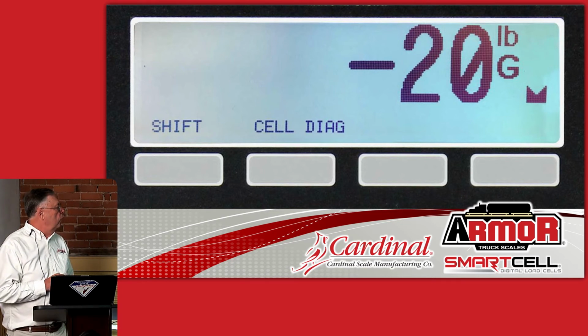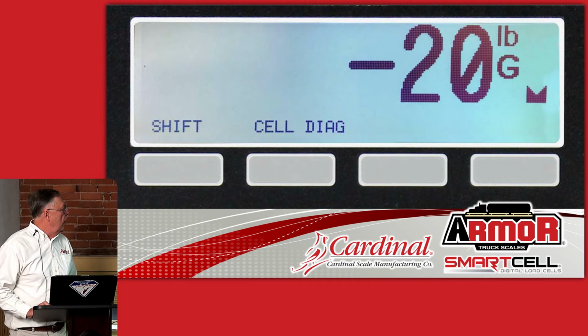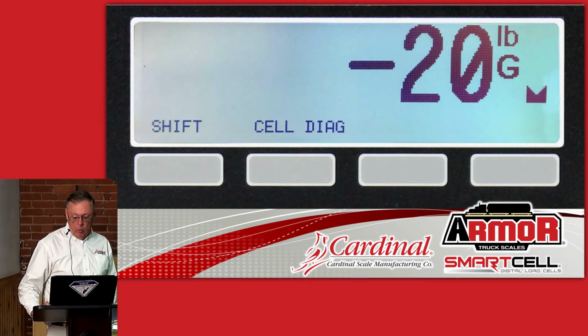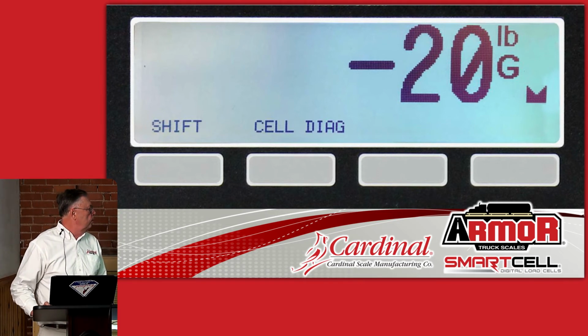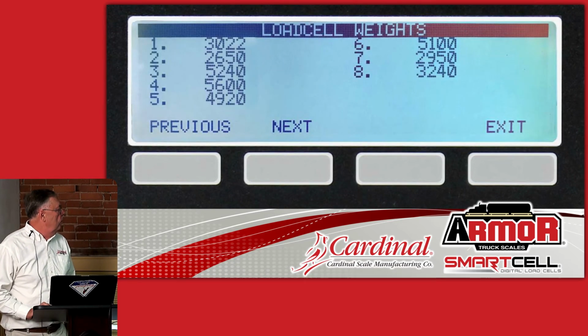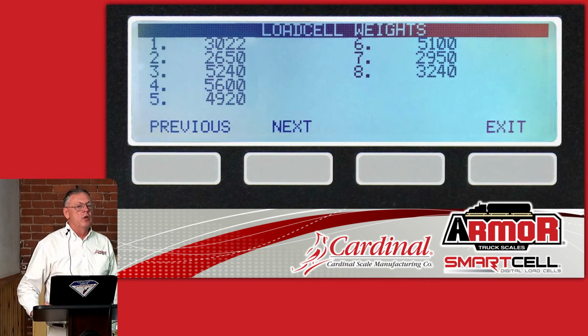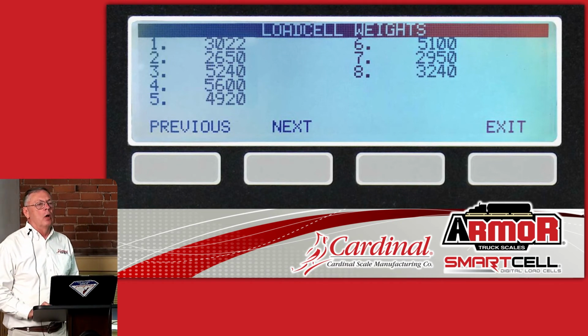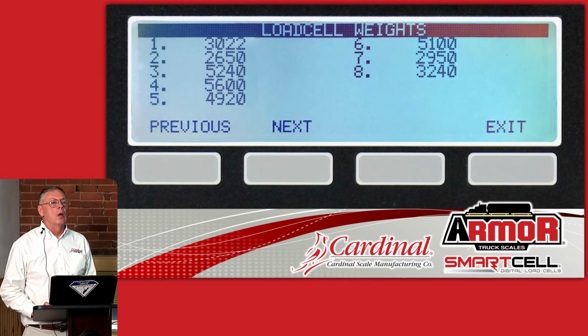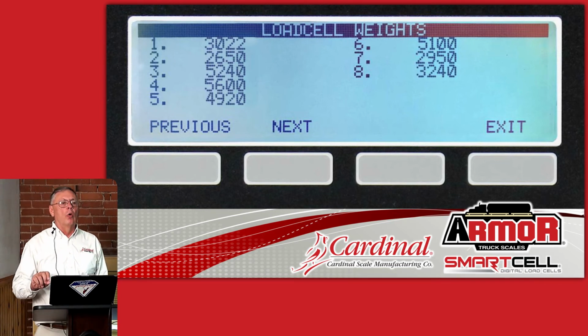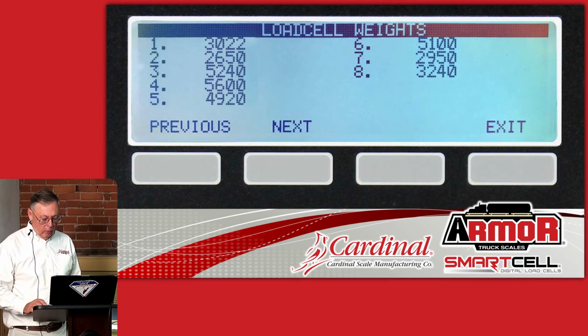To get to the diagnostics, you'd press the red button in the middle of the arrow keys, and the cell diagnostics button comes up, and you'd push that second soft key there. This first screen shows the actual weight coming off of each load cell. Now, normally that's going to be just the weight of the weighbridge sitting there. If you have a load cell and you jack the weighbridge up at load cell number 1, that reading should go back down very close to 0, within the 0 balance tolerance.